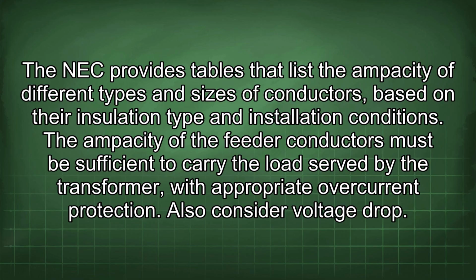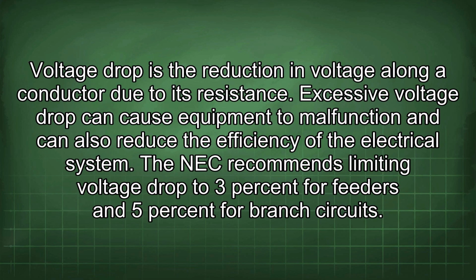Also consider voltage drop. Voltage drop is the reduction in voltage along a conductor due to its resistance. Excessive voltage drop can cause equipment to malfunction and can also reduce the efficiency of the electrical system. The NEC recommends limiting voltage drop to 3% for feeders and 5% for branch circuits.